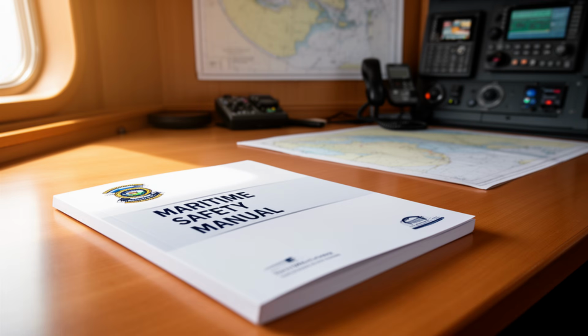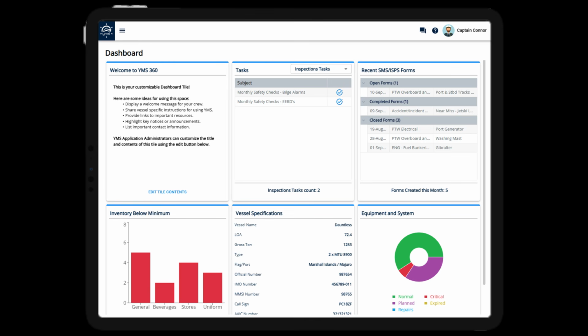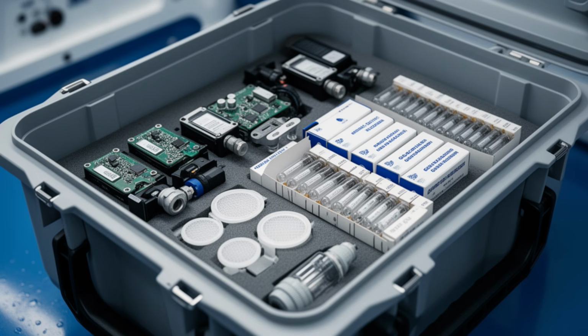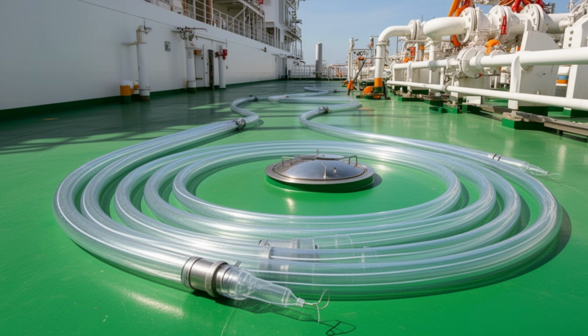The surveyor will spend a lot of time reviewing your documentation. Let's see what needs to be in order. Every instrument must have a manual available in the working language of the ship. This is a common point for observations. Maintain an up-to-date inventory of all instruments, spare parts, and test gases carried on board. Always check the expiry date on your span gas cylinders. Using expired test gas is an automatic negative observation. Ensure you have sufficient spares and consumables, like detection tubes or chips, specifically for the toxic gases in your cargo. Verify that your sampling hoses are long enough to reach the bottom of the deepest tank on your vessel.